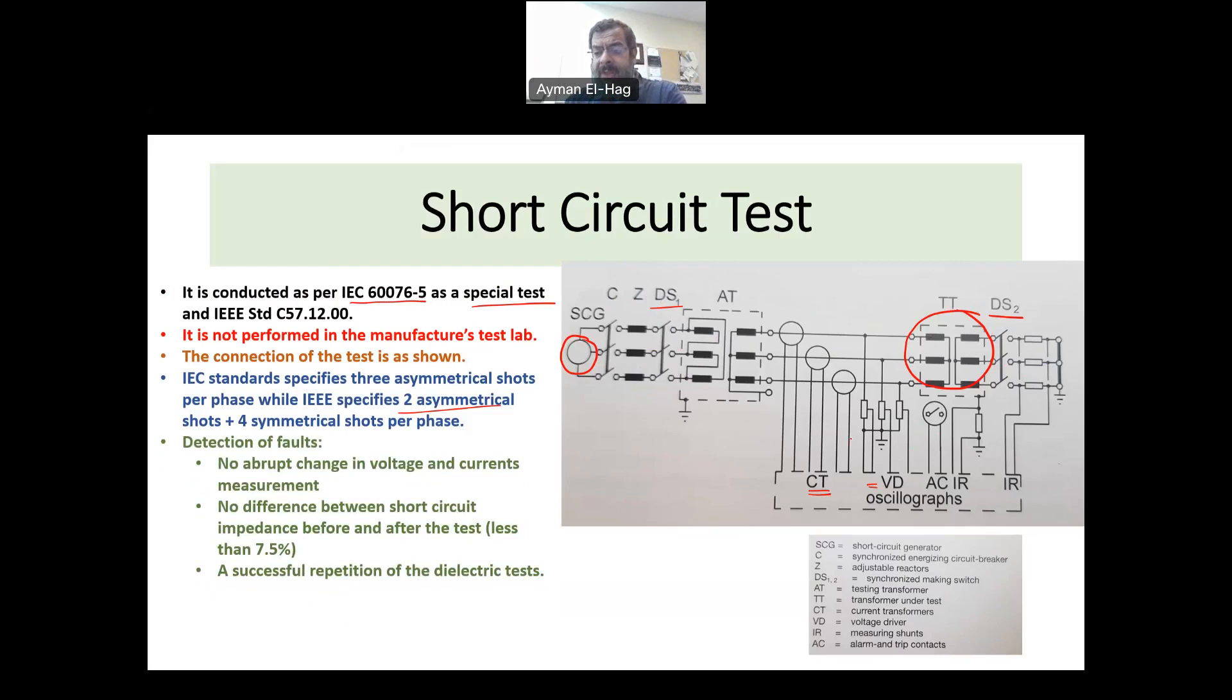During the test, you will be measuring the voltage and the current. So if there is any abrupt change in the voltages or currents, like a collapse of the voltage or the current, sudden collapse, then you know that the transformer has failed the test.